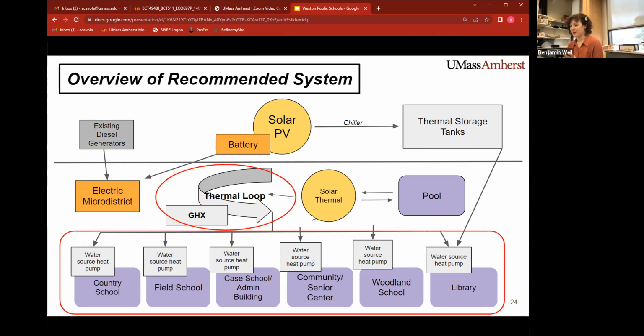So this diagram shows how these elements fit together. Here's how the components of the system work together. Water is circulated through the geoexchange field, and the ambient temperature water is distributed to the individual buildings through the thermal loop. And at each building, a water-to-water heat pump adds or extracts heat from the water in the ambient loop. The building supply water circulates through the building's distribution system and conditions the space. And in the upcoming slides, I'll be explaining how system performance can be further enhanced by integrating solar thermal heating. And that also has an unexpected side benefit. So stay tuned.